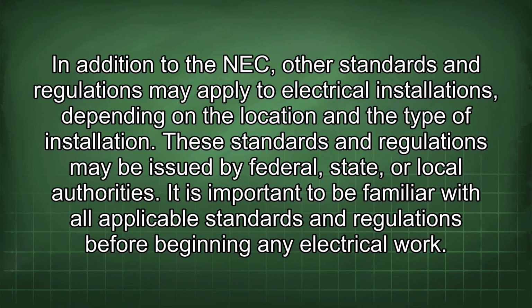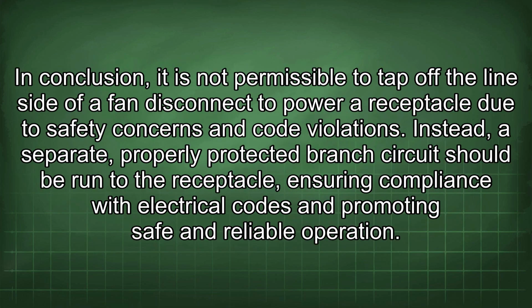In addition to the NEC, other standards and regulations may apply to electrical installations depending on the location and the type of installation. These standards and regulations may be issued by federal, state, or local authorities. It is important to be familiar with all applicable standards and regulations before beginning any electrical work. In conclusion, it is not permissible to tap off the line side of a fan disconnect to power a receptacle due to safety concerns and code violations. Instead, a separate, properly protected branch circuit should be run to the receptacle, ensuring compliance with electrical codes and promoting safe and reliable operation.